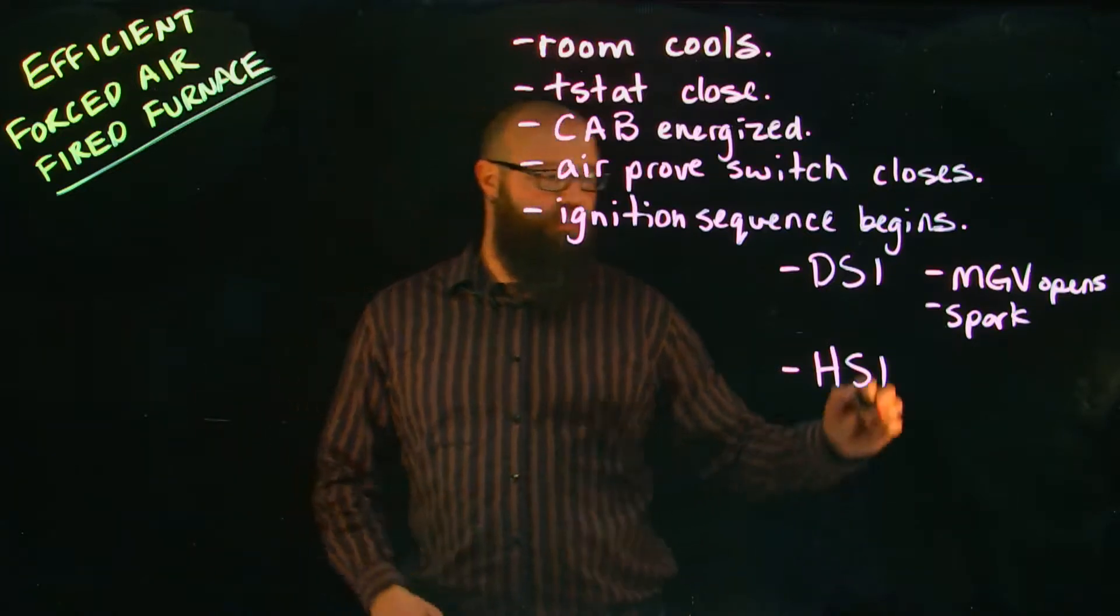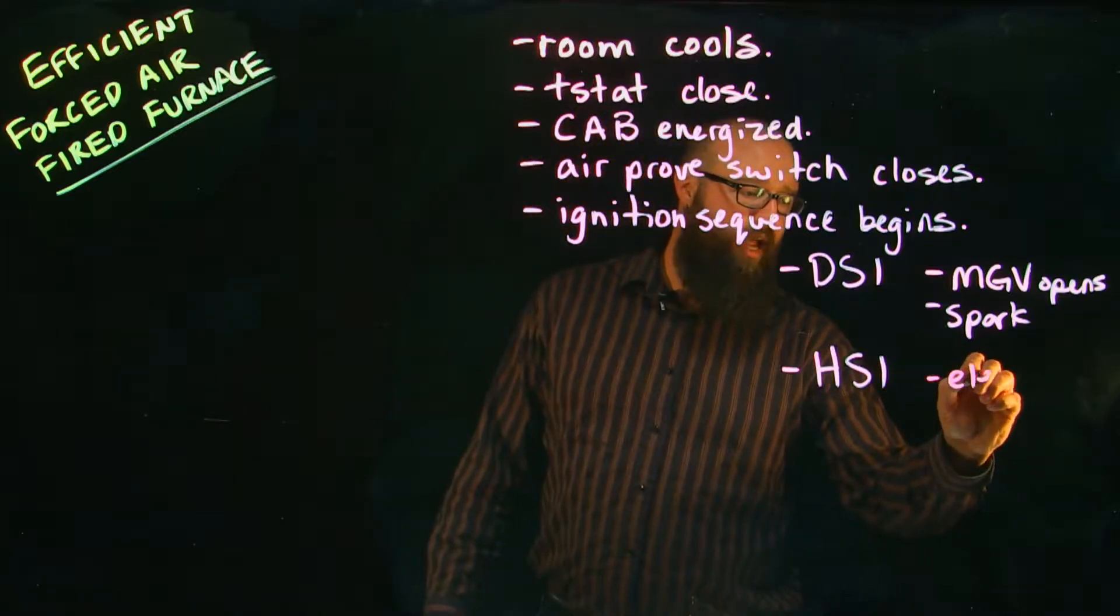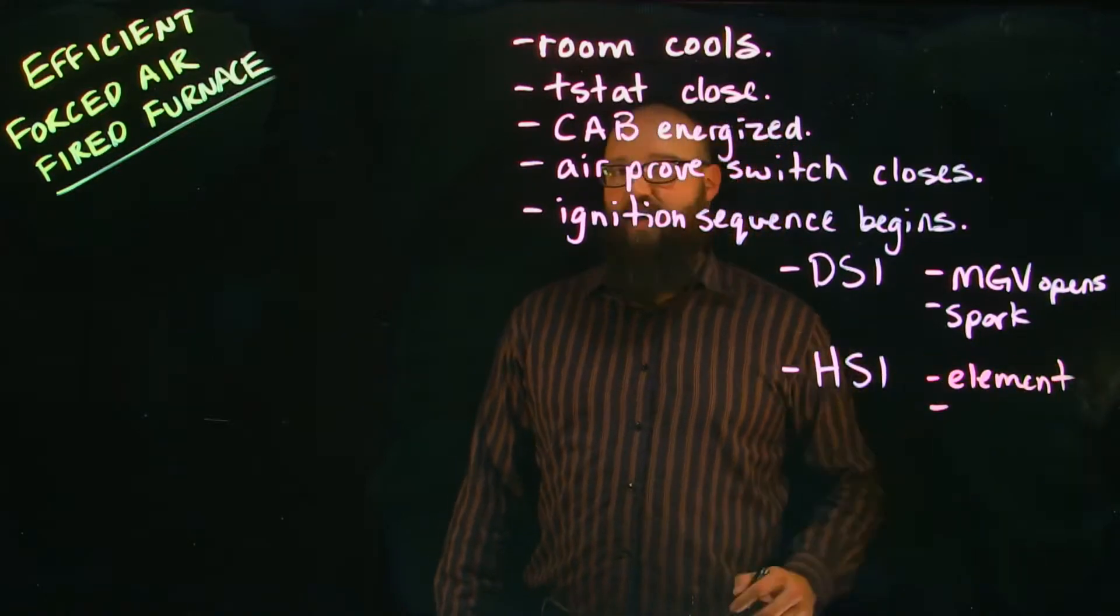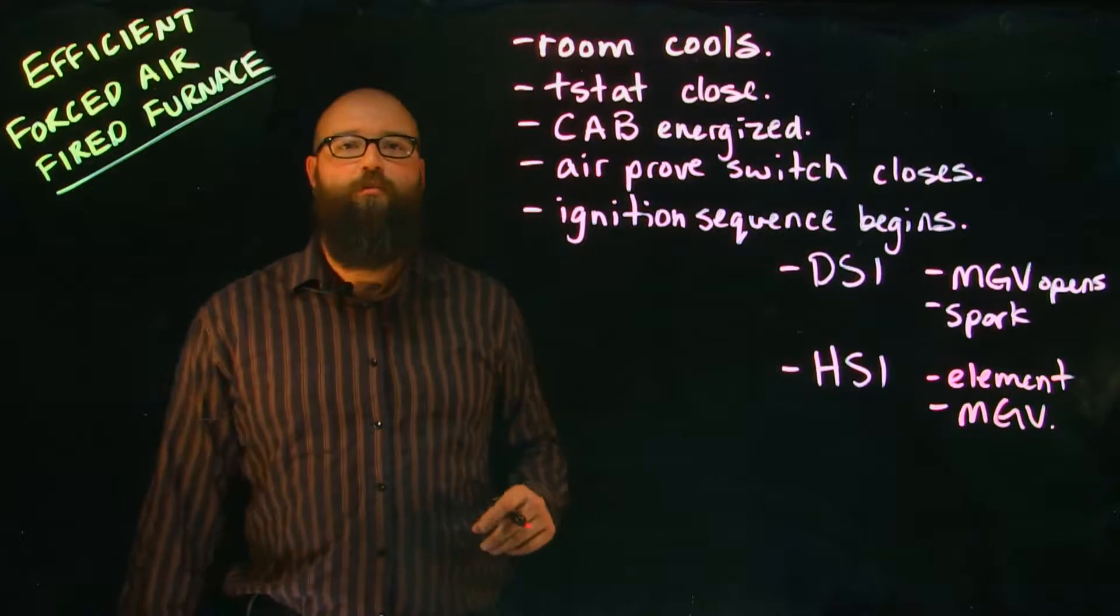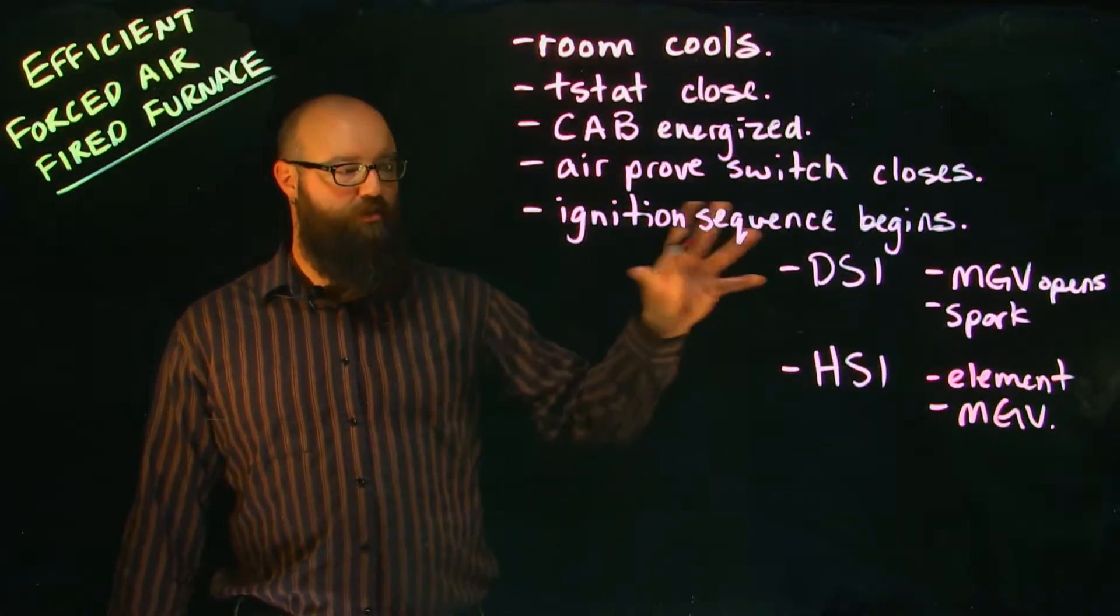So in an HSI, element energized first, then the main gas valve opens after a predetermined amount of time, exposing that gas to that superheated element.